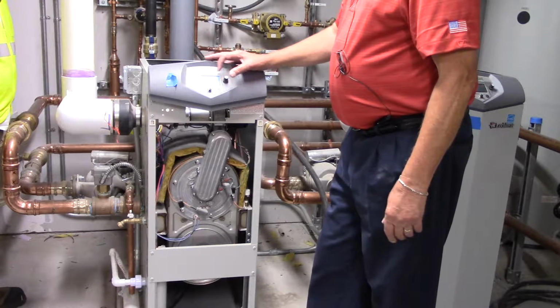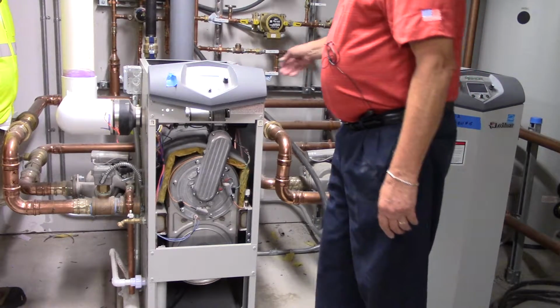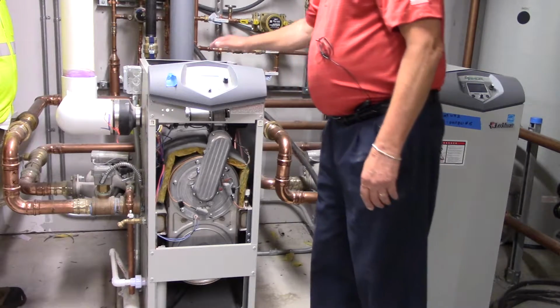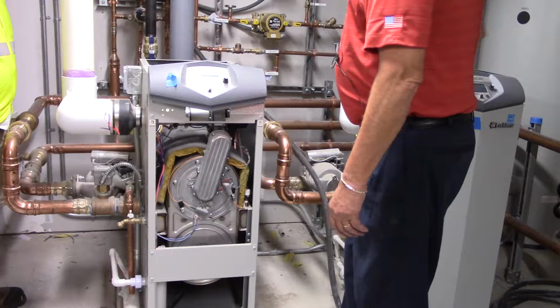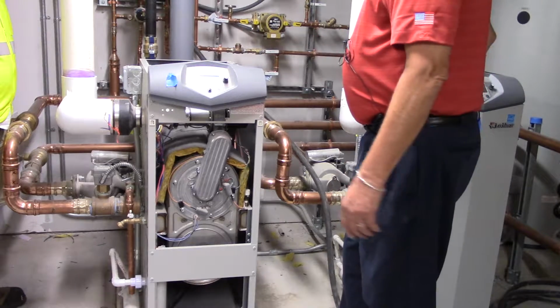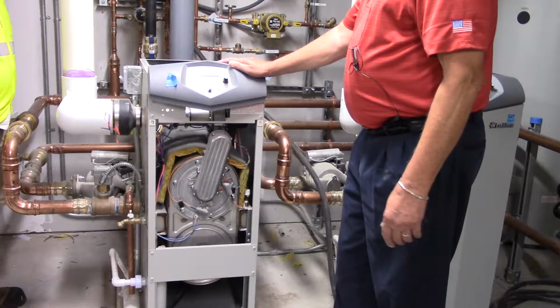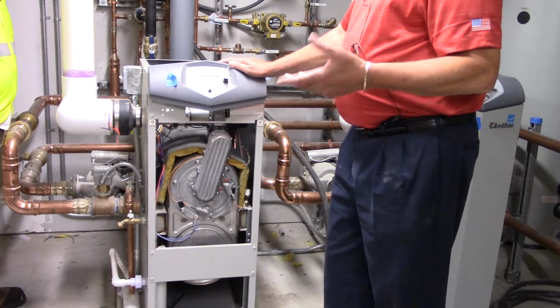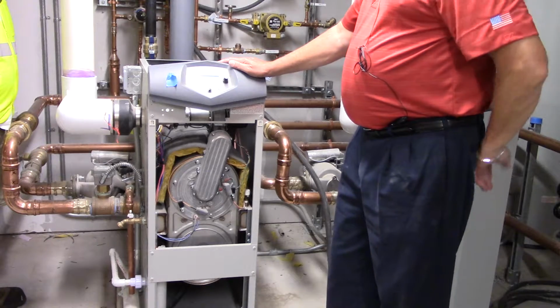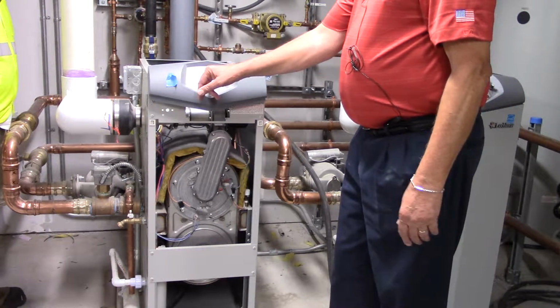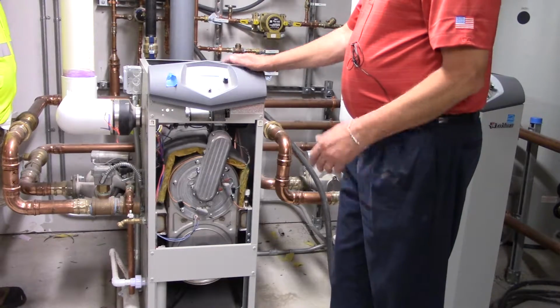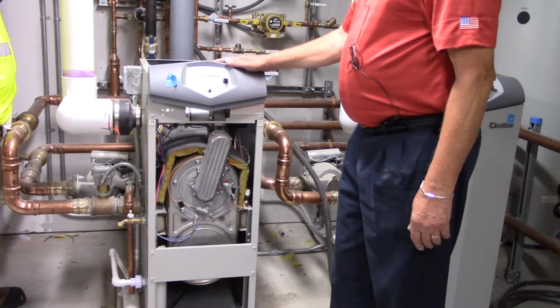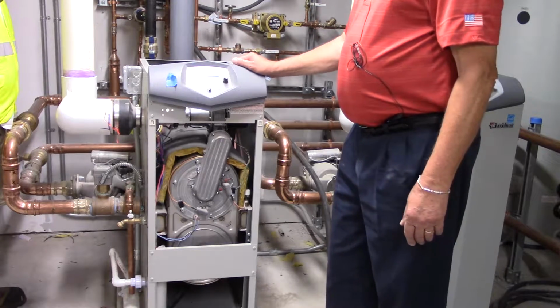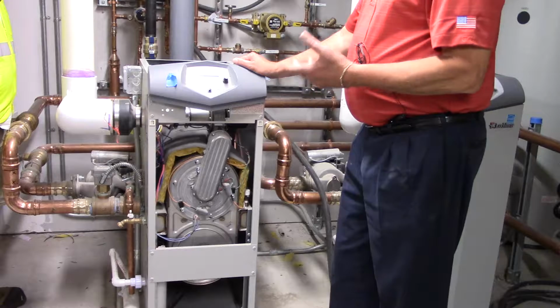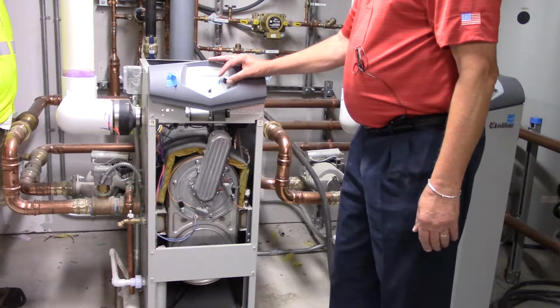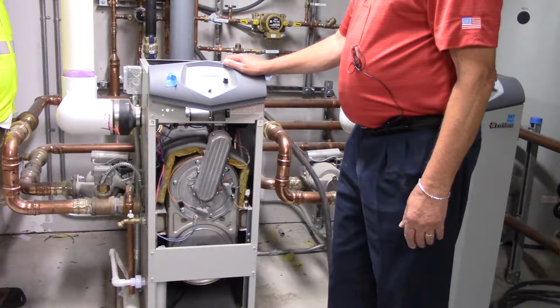And then you've got the cascade screen. These 2 units are cascaded together. They've got a 3-wire shielded cascade. What that means is you've got a leader and you've got a member. They will alternate after 40 hours of runtime. And you'll be surprised at how close at the end of a year the runtime on these 2 units is. It's generally within 10%. When you look at this, it's going to say 0 and 1 are present. That means that we're seeing both boilers. This is 0, this is 1, and if it's flashing, it's running. So if you see something flashing and it's not running, then that's a problem. And then just back to the main screen.